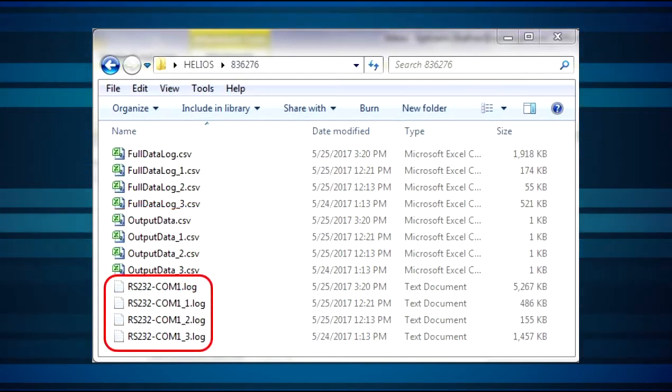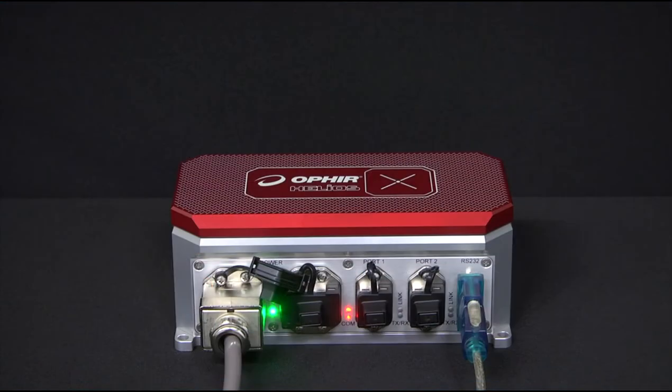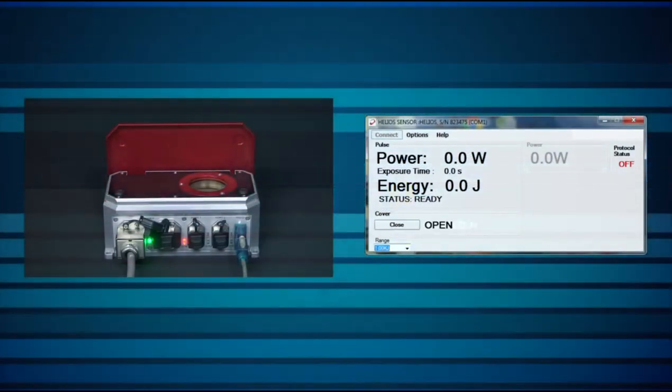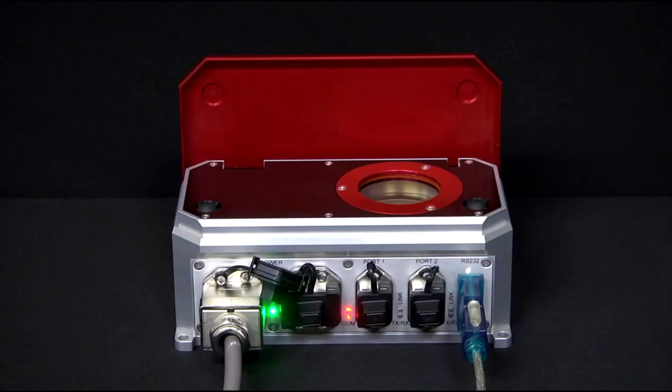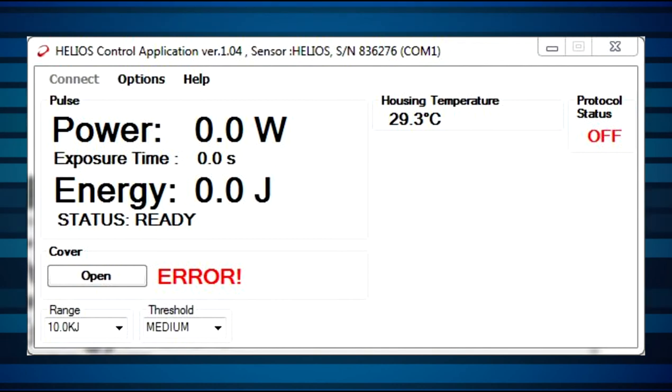The Helios has a protective cover that can be opened and closed remotely to protect the sensor when not in use. The cover is initially closed. After clicking Open, the message 'In Motion' flashes until the cover is in a fully open position. After opening completely, the status changes to Open, and pressing the button Close will close the cover. If some problem prevents the cover from completing its movement to open or close, this will time out and an error message will display to alert the user.